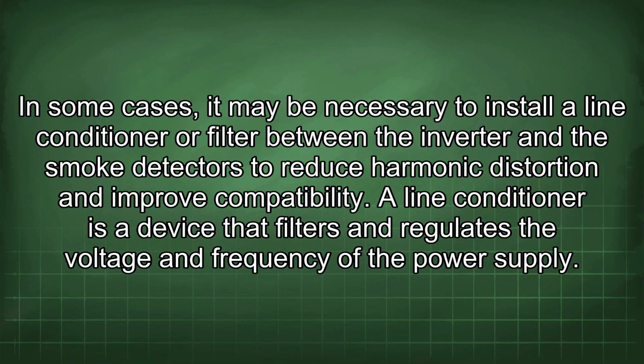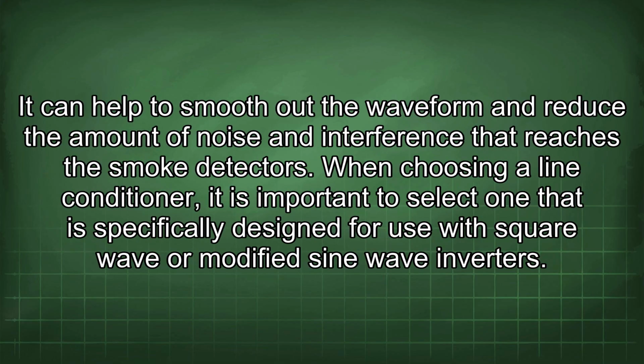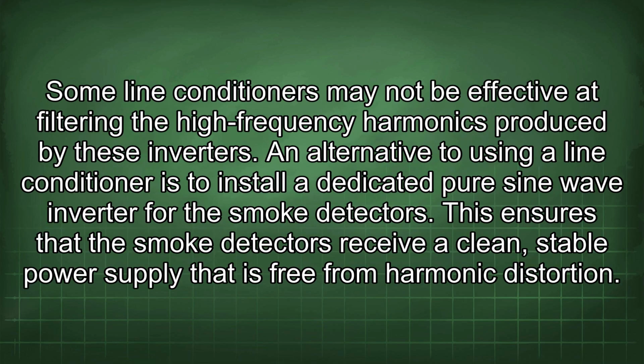A line conditioner is a device that filters and regulates the voltage and frequency of the power supply. It can help to smooth out the waveform and reduce the amount of noise and interference that reaches the smoke detectors. When choosing a line conditioner, it is important to select one that is specifically designed for use with square wave or modified sine wave inverters. Some line conditioners may not be effective at filtering the high-frequency harmonics produced by these inverters. An alternative to using a line conditioner is to install a dedicated pure sine wave inverter for the smoke detectors.